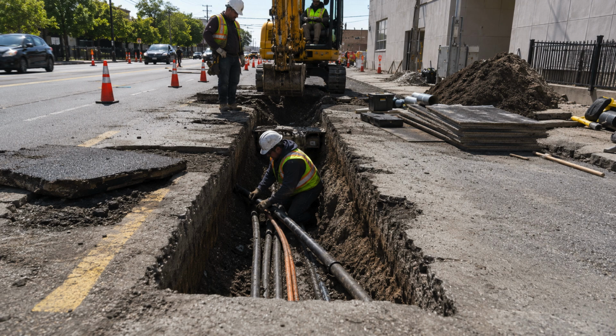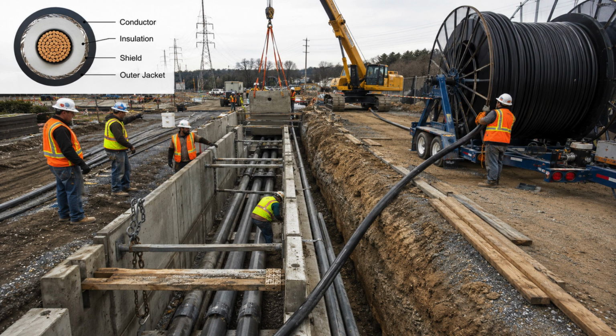It is often targeted. Now, there is another trade-off that people do not always consider. Underground systems can be less exposed to storms, but when they do fail, they can be harder and slower to repair. With overhead lines, damage is often visible. A broken pole, downed wire, or blown transformer can be found quickly. With underground systems, the problem may be hidden below the surface. Crews may need specialized fault locating equipment to identify where the cable failed. They may need access to underground vaults or pull cable through conduit. If the cable is directly buried, repair may require excavation. If the failure is under a road, sidewalk, driveway, or landscaped area, restoration becomes more complicated.